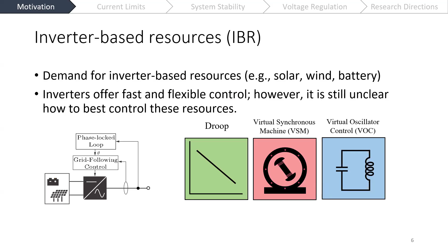Some examples of events somewhat recently. Here, back in 2024 in California, after a typical fault was cleared, during the fault, 532 megawatts of inverter-based resources decided to disconnect from the grid instead of remaining connected, prioritizing protecting themselves instead of continuing to provide power to the system. Luckily, there weren't any cascading faults following this, and the grid was able to recover, and those inverters were able to connect back to the system. But it shows a clear need for stronger controls for these systems, or at least an ability for them to handle typical faults that happen in our system often, especially as we get higher and higher penetrations of inverter-based resources.